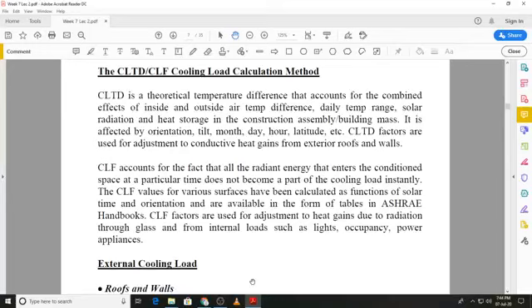That means if at 9 a.m. you have a building in Karachi, and if you have a building exactly the same in Lahore at 9 a.m., the radiation incident will be different because the latitudes are different. And in addition to all those, there is the type of construction. If you have a wall, the wall can be constructed of, let's say, concrete blocks. A wall can be made from layers of other materials. They can be wooden sheets or insulation inserted over there. You can also have hollow concrete blocks.